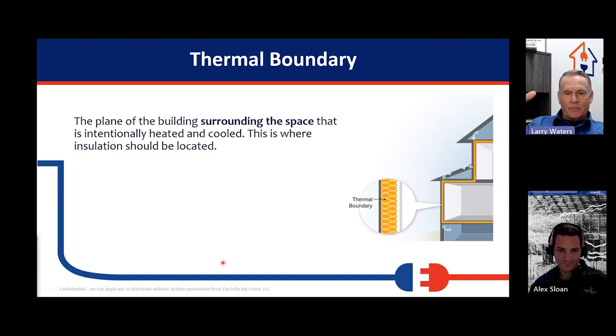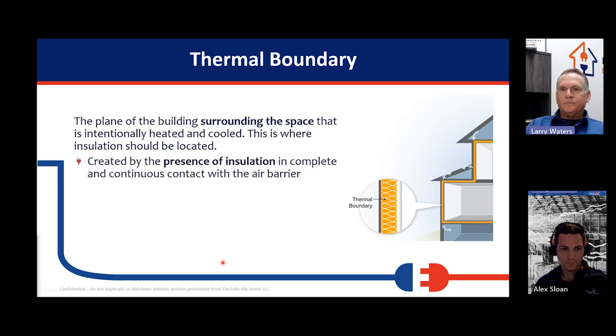If we have a chase that goes up into the attic from the downstairs where the ducts are going through, and there's an opening there, that is a break in the thermal boundary if insulation is covering it. Anywhere where you go into an attic space and you see insulation, but there's a hole underneath and it's not making direct contact with the ceiling or walls, that is a break in the thermal boundary. So the plane of the building surrounding the space that is intentionally heated or cooled needs to have insulation up against the air barrier that creates the thermal boundary.